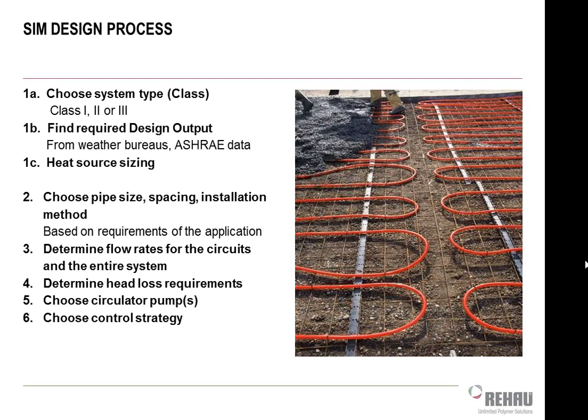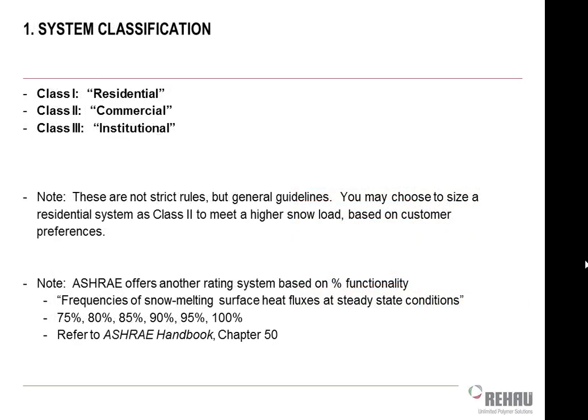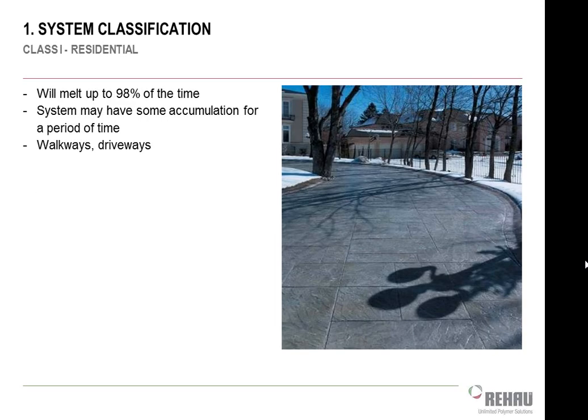But once we're able to do that, we can use that to base the size of the tubing that we're going to need, size our pumps based on that same kind of drill we talked about a minute ago. And we'll work that all the way back to our boiler plant. So that'll size our pipes, it'll size our circuits, it'll size our pumps, it'll determine our spacing and all that kind of stuff. So control strategy is the one that's going to be a little bit more interesting, how we choose to run it. Like I said, there's technically 3 classes: residential, commercial, institutional, and it really is going to depend on how we decide to control this.